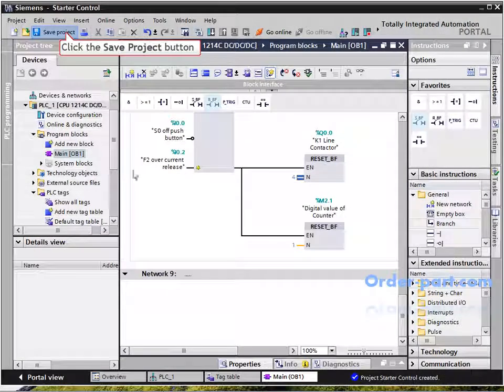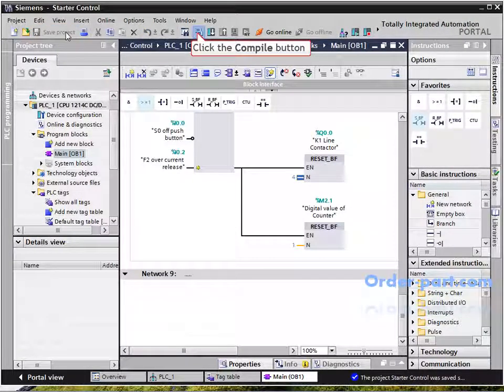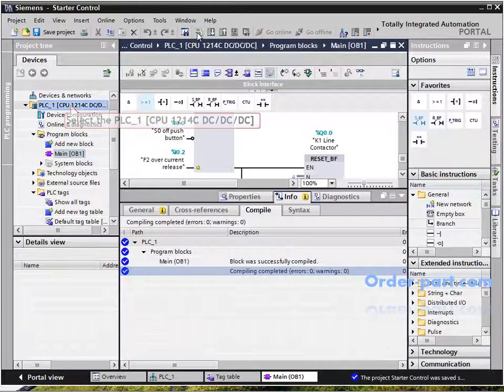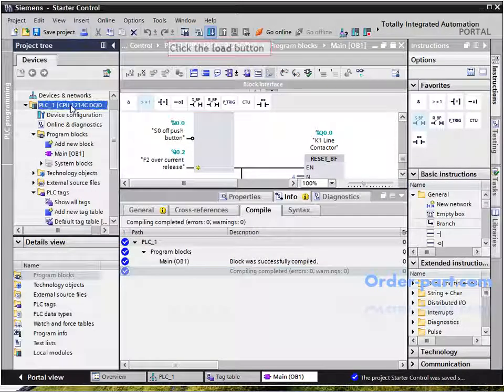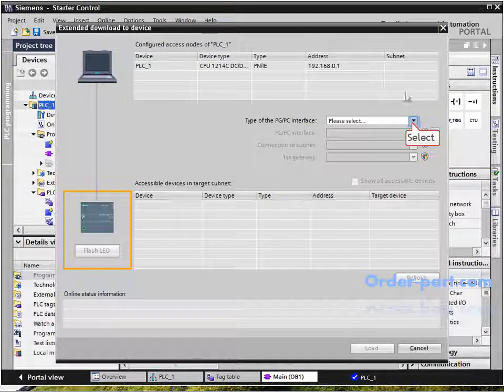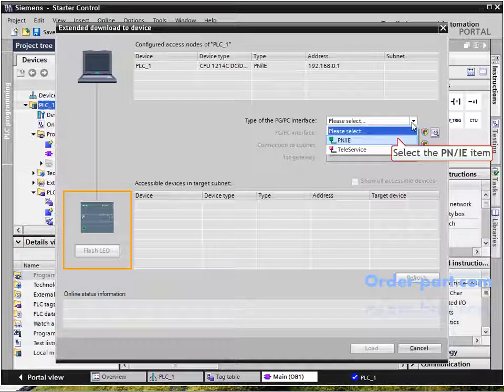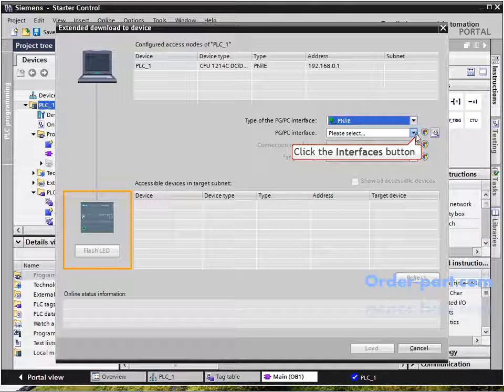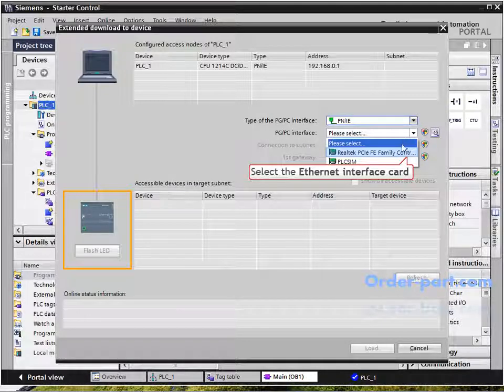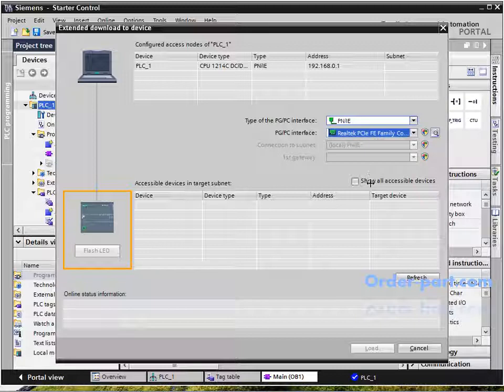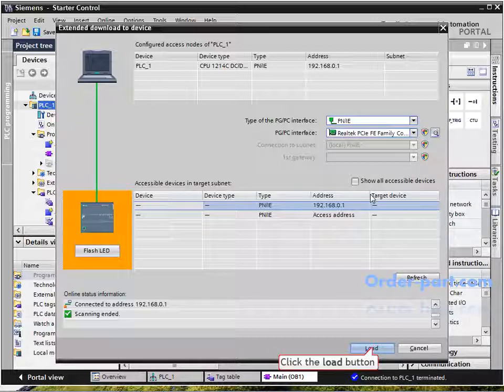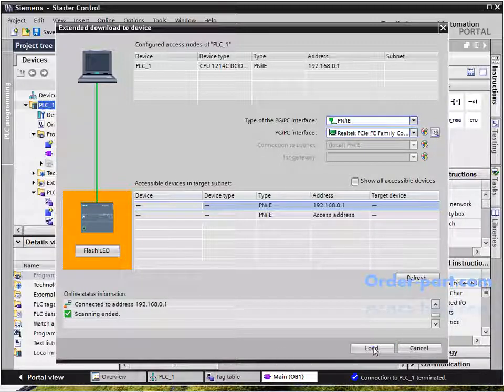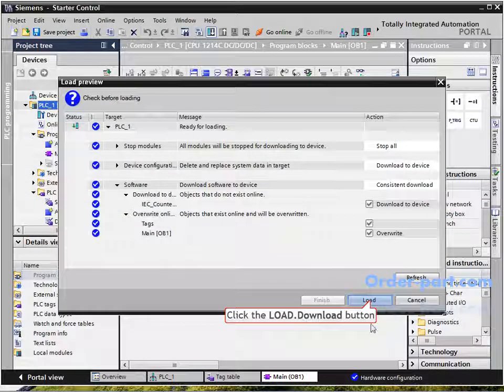Now save the project and compile it for errors. Select the PLC and then download it. Select the type of PC interface as PROFINET as shown. My PC interface is Realtek — it may differ in your case. If there is a problem downloading, check your PC IP address as shown in our previous underground car parking project video; it should be in the same subnet mask.